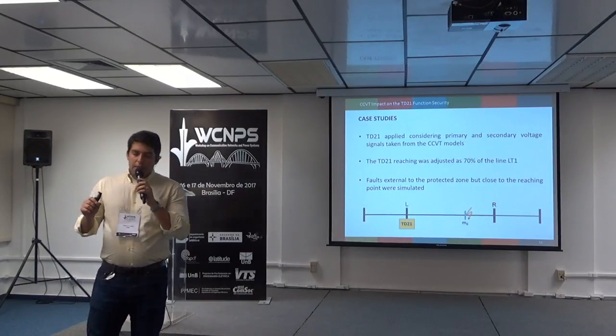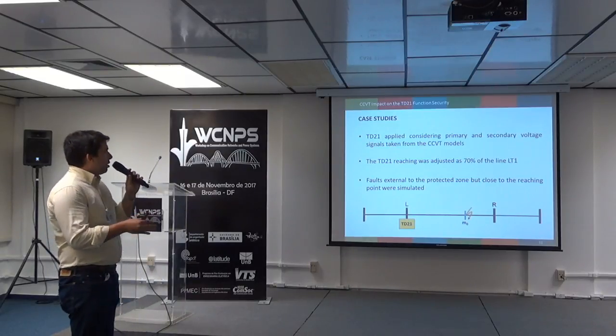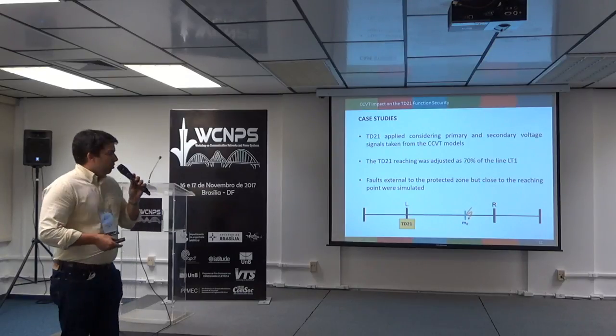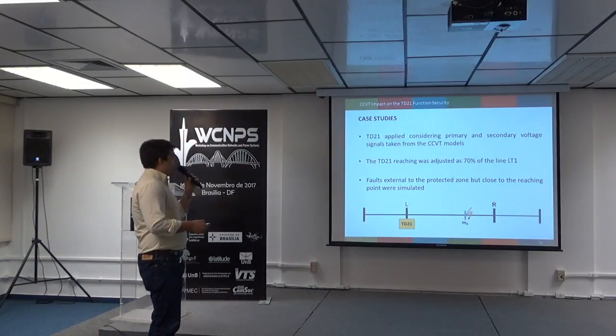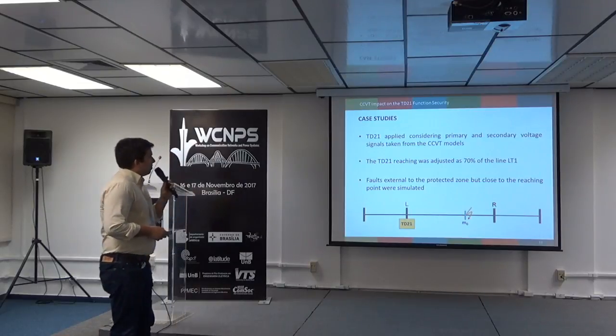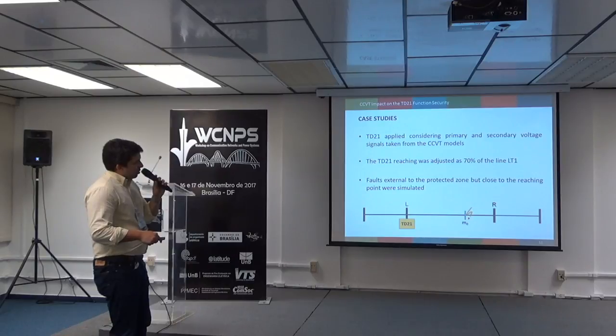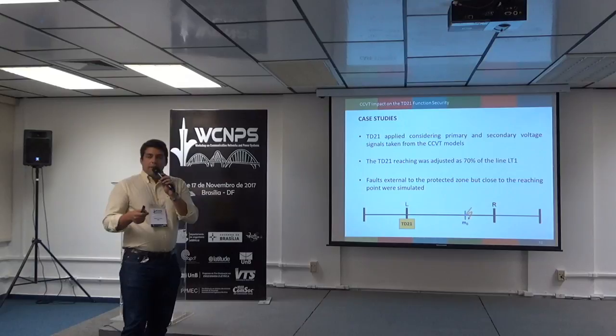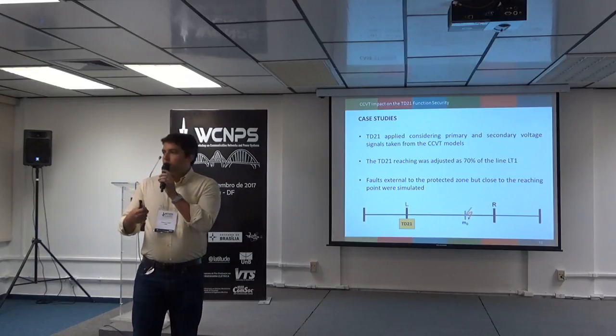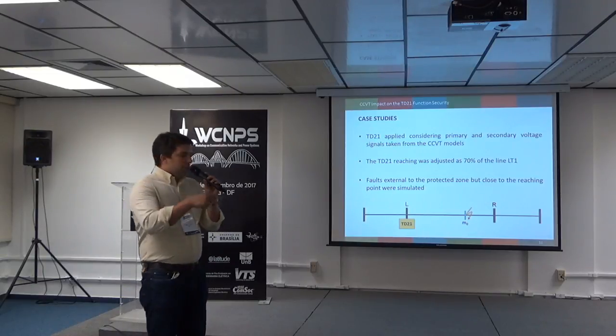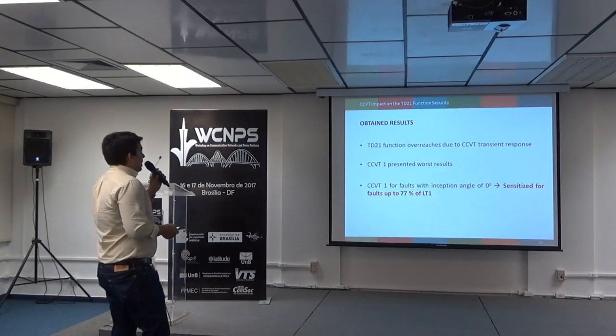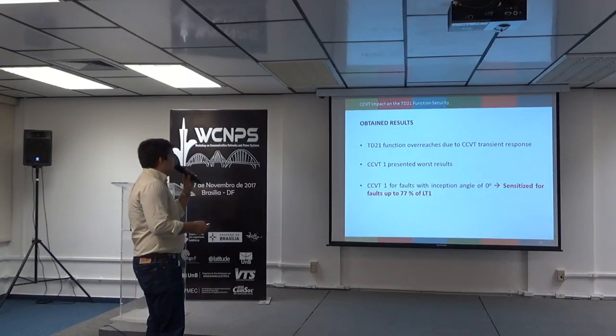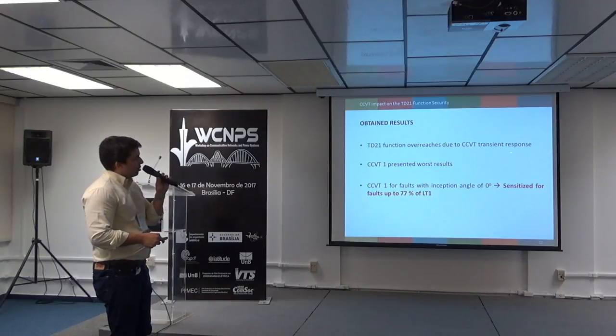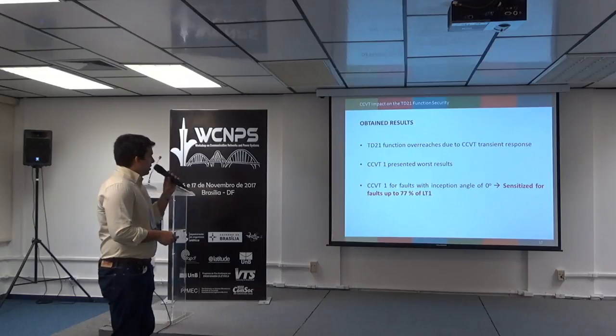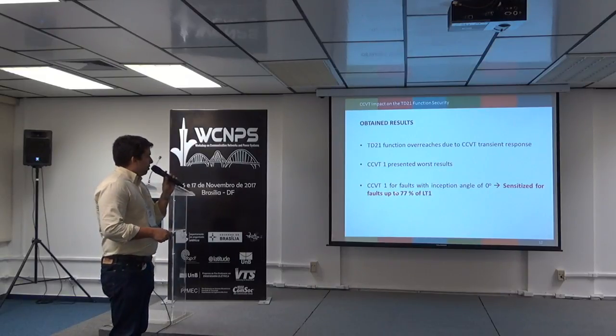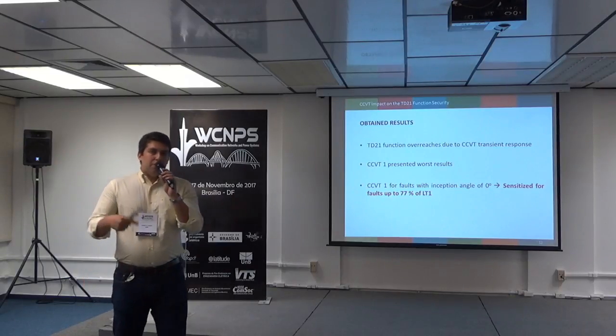Among the case studies, in all simulations, both primary and secondary voltage signals were taken into account during the application of the TD21 function, and the reach of this protection function was adjusted to 70% of the protected line. Faults external to the protected zone but very close to its reach were simulated, just to evaluate if the TD21 would have problems when the CCVT was used in each case. About the obtained results, preliminary in this case, the TD21 function showed overreach due to the CCVT transient response. Among those three CCVT models, the CCVT1 presented the worst results since it was sensitized for faults up to 77% of the protected line, even using a reach point at 70%.